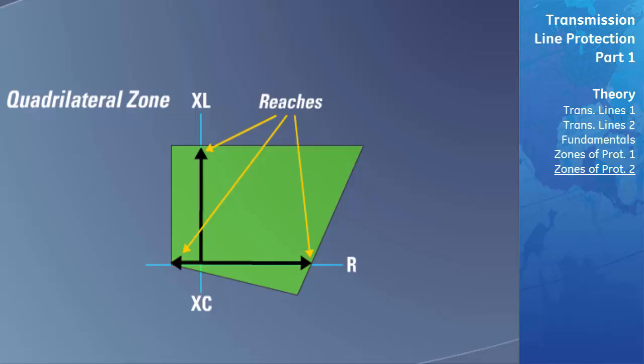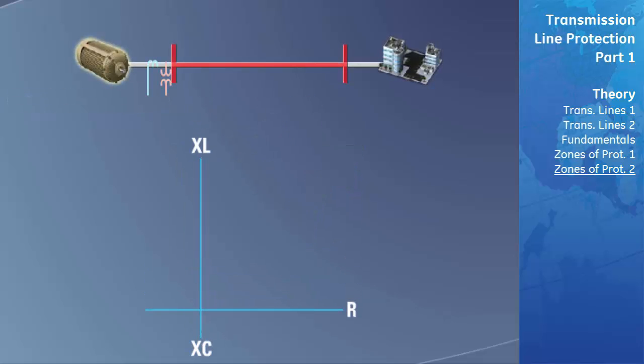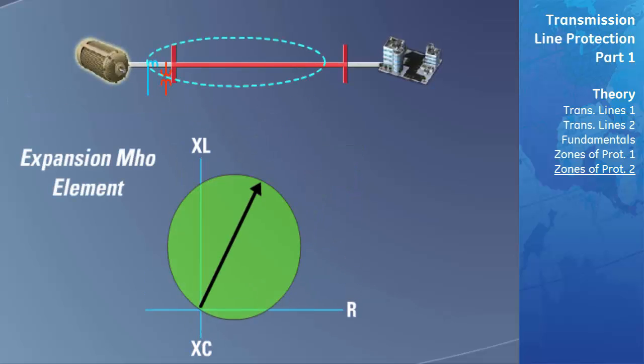Some advanced distance relays have added features to the Mho circle characteristic to increase security and reliability for faults that occur very close to the point of measurement, which is at the beginning of the transmission line. This point of measurement is shown at the origin of the RX diagram. On faults that occur very close to the point where the currents and voltages are being measured, some relays may have difficulty distinguishing whether the fault is inside or outside their zone of protection. To overcome this difficulty, the relay can change the size of the Mho circle when the calculated impedance is very near the origin. This is sometimes referred to as an expansion Mho element.